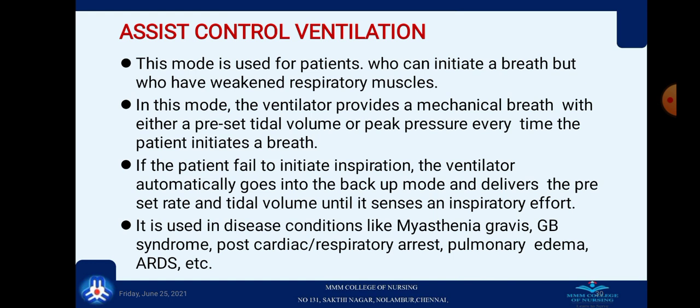Next we can see the assist control ventilation. This mode is used for the patient who can initiate a breath but who has weakened respiratory muscles. In this mode, the ventilator provides a mechanical breath with either the preset tidal volume or peak pressure every time the patient initiates a breath.